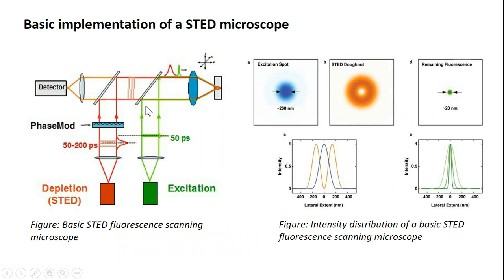In the basic implementation of a STED microscope, we use an excitation laser as in confocal microscopy, but additionally we use a STED beam which is phase modulated and red shifted. The excitation creates a spot as in confocal, while the STED beam forms a donut shape incident on the sample except at the central focal point. This is why we can achieve resolution of 20 nanometers. Only the central focal spot is allowed to emit fluorescence while others are depleted.